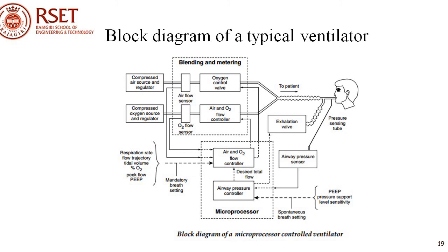During the inspiratory phase, a certain gas volume is delivered into the system, resulting in the increase of the airway pressure and alveolar pressure, with the airway pressure always being higher than the alveolar pressure. When the pressure of the patient circuit and alveolar pressure becomes equal, the inspiratory flow ends and expiratory flow begins, and the pressure in the patient circuit is allowed to decrease.